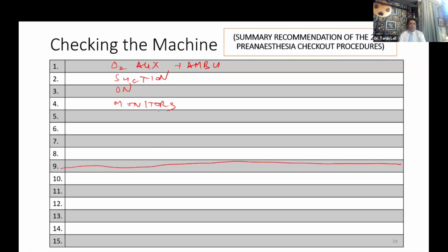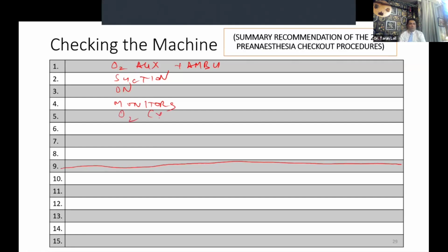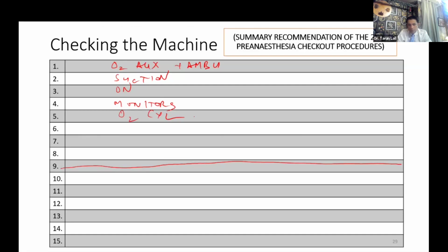So high pressure, now I will check the oxygen cylinder, which is behind my machine. The pressure in a full cylinder is 150 bars. So for the emergency, I will have at least 100 bar pressure so that it should last me for a few minutes in case the medical gas pipeline goes off. And in case I don't have a medical gas pipeline, then I'll make sure that 2 full cylinders are attached to the machine and I have a sufficient stock of full cylinders to change whenever the oxygen runs low.